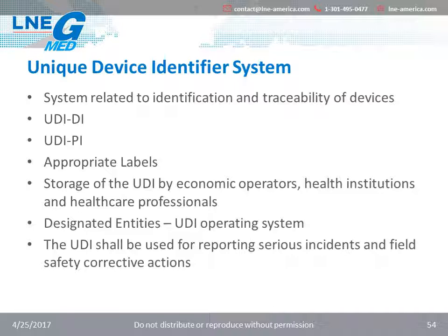UDI will result in label changes as it is required to appear on any packaging or labeling. Storage of UDI. What this means is that economic operators will store the UDI, preferably electronically, of certain categories of devices with which they have either been supplied or with which they have actually supplied.